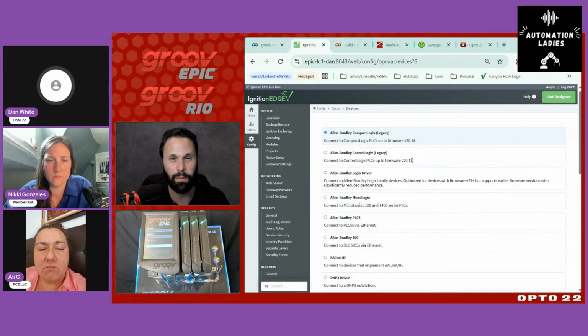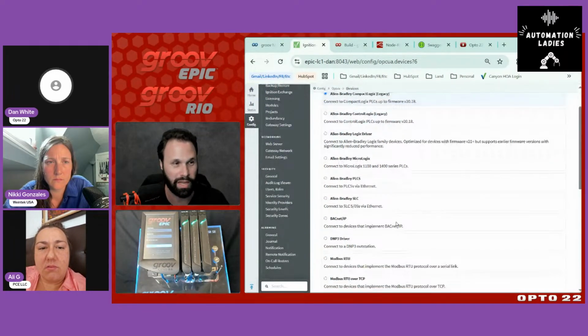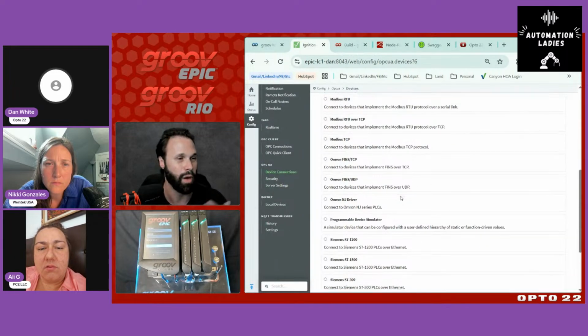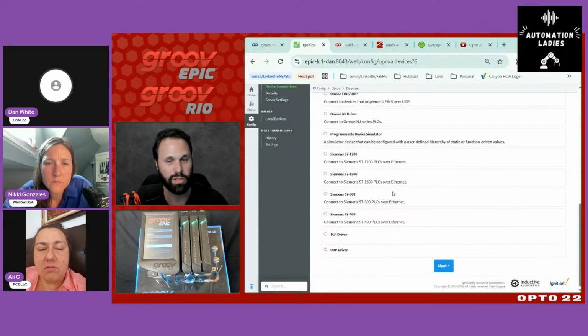However, if you use the EPIC as your gateway, you can have all of that data aggregated by the GRV-EPIC using a tool like Ignition. You can see the driver libraries here: Allen Bradley, BACnet, Modbus, Omron, Siemens, and so on.